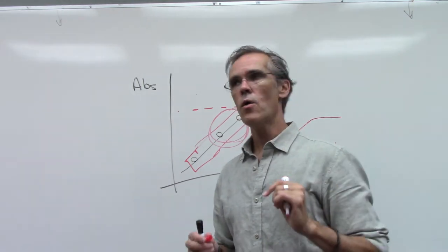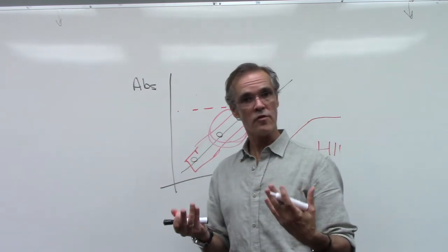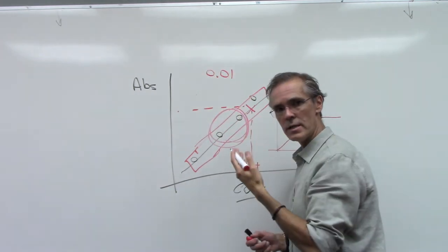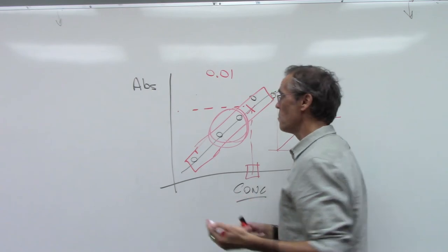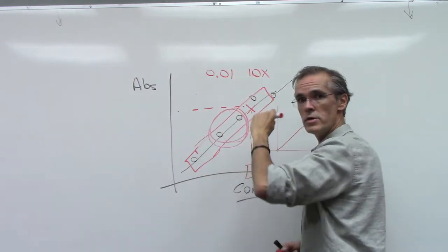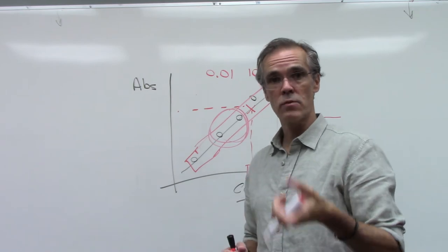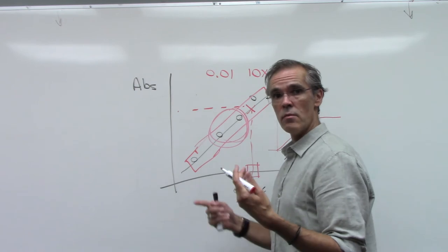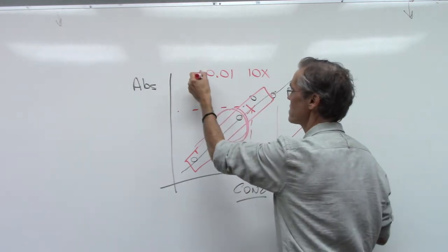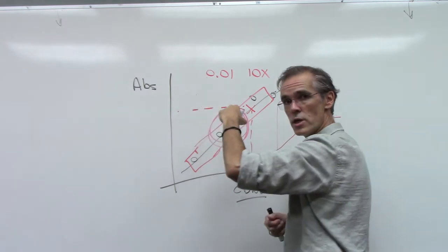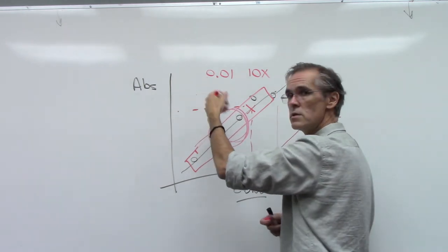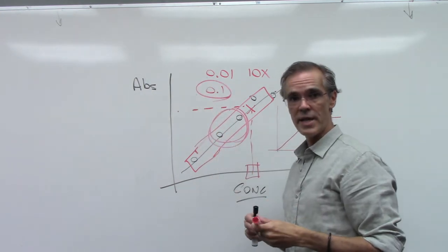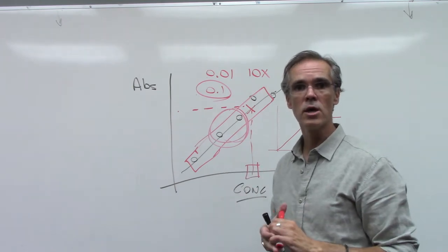Don't select something at the delimitation, don't tempt fate, just go in the middle there. Once you know that, remember the dilution factor. For example, if you have a value of 0.01 when you measure it and you diluted it 10 times, well what you need to do is multiply that value by 10, and that gives you 0.1, that's the accurate value.